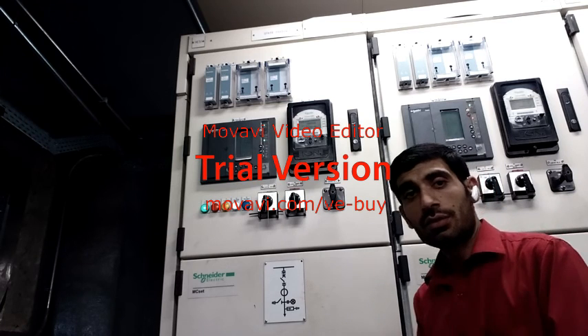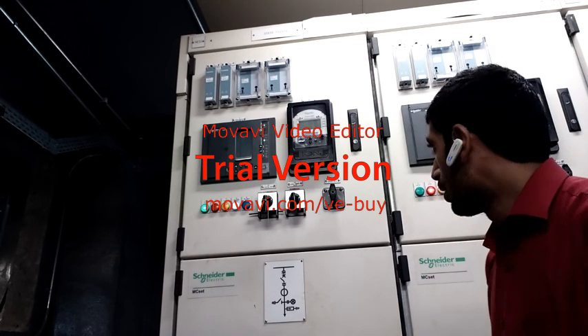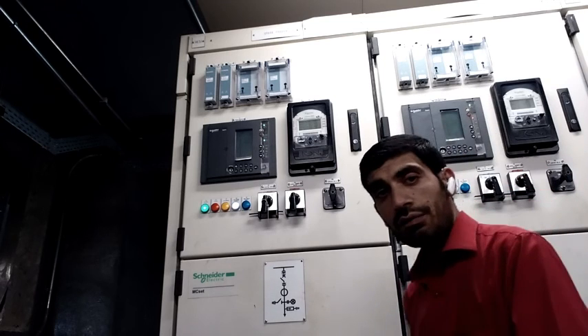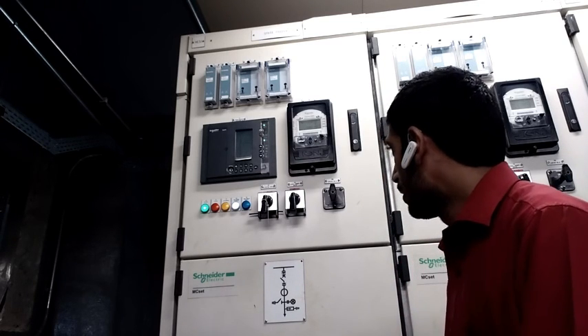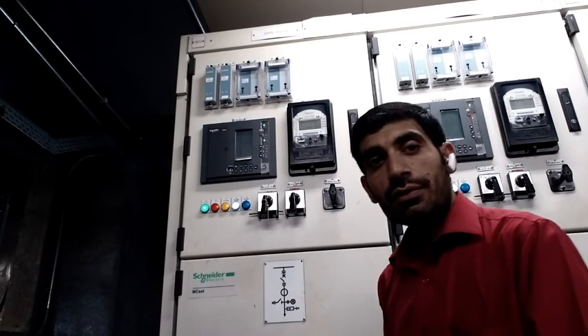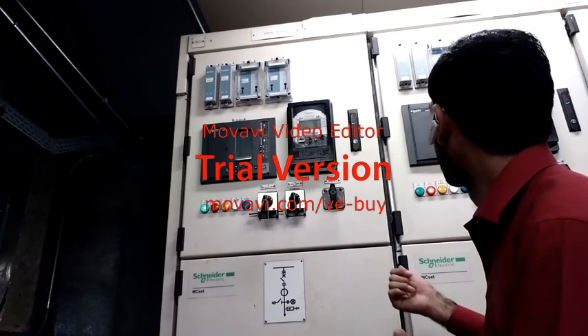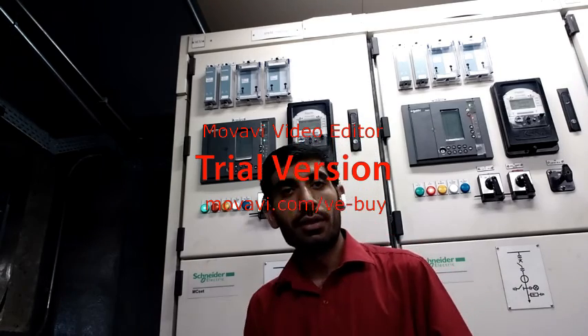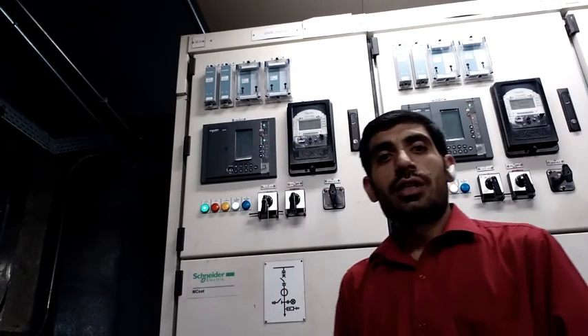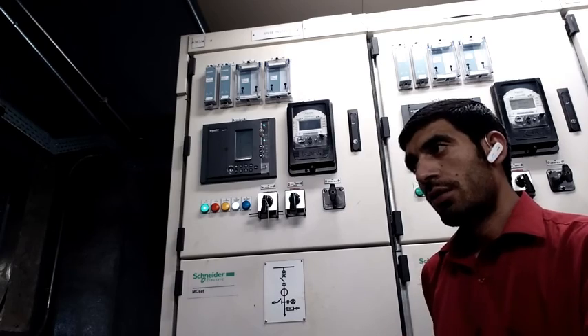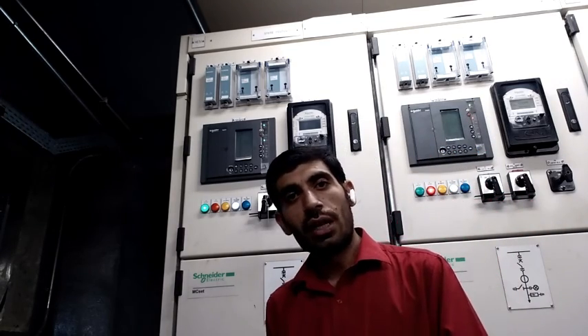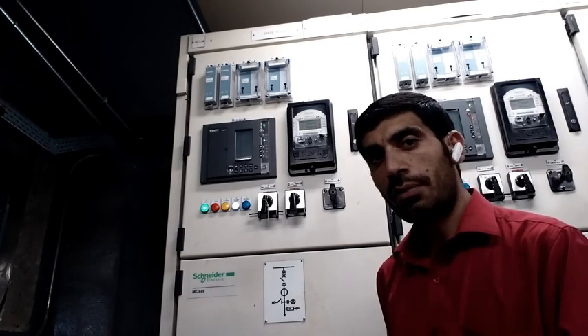And this lockout relay will also be tested through Freja. We inject 125 volts DC through Freja and check the timing, how much timing it takes for tripping. And all these things I want to explain to you. And the breaker test, the breaker timing test, we test through the EGIL breaker timing test, with a graph for closing timing, for opening timing, and opening and closing timing with graph through EGIL.